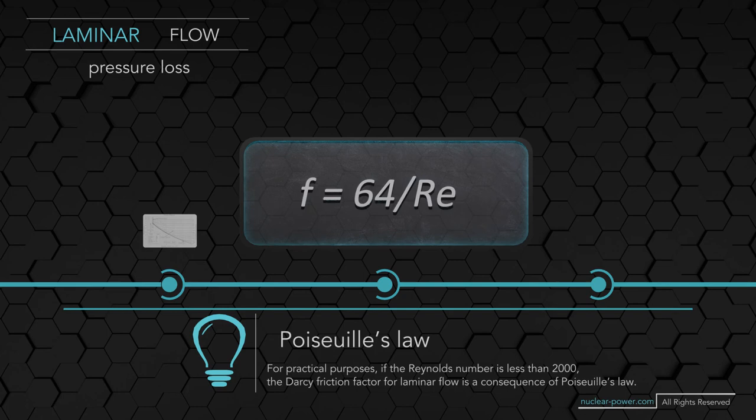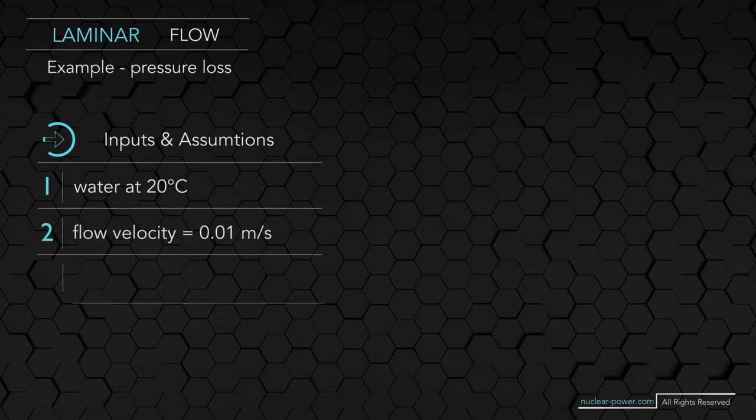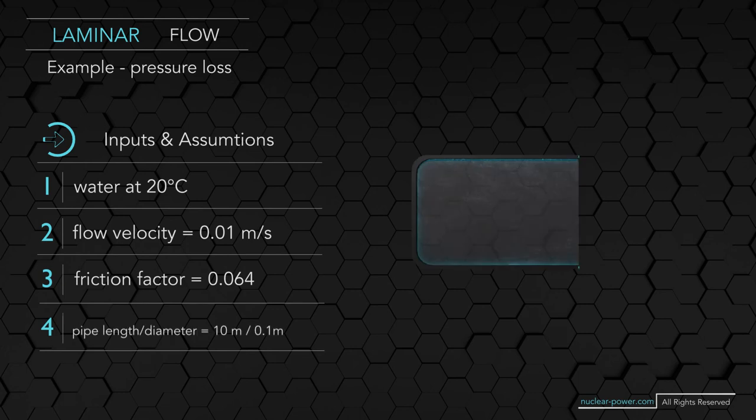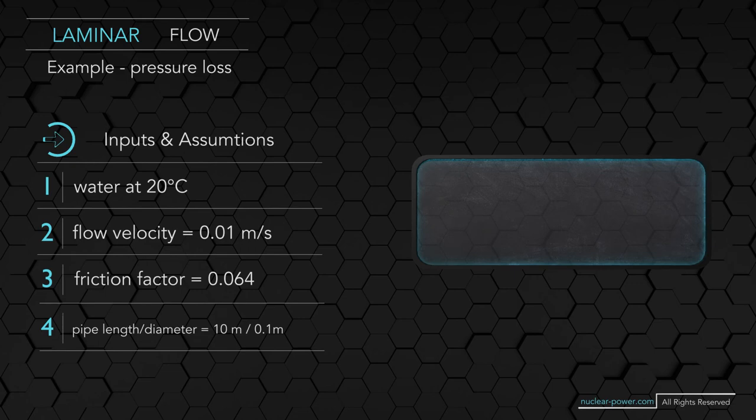For example, let's calculate friction losses that occur in pipe flow due to the effect of the fluid's viscosity near the surface of the pipe. We will assume similar calculation inputs as in the previous example, but we will assume the flow velocity to be 0.01 meters per second. The resulting Reynolds number for water flow in a circular pipe with a diameter of 10 centimeters, where the dynamic viscosity for water at 20 degrees Celsius is 0.001 pascal seconds, is 1000. Using the Moody diagram, we determine the friction factor to be 0.064. Using the Darcy-Weisbach equation, we determine the resulting pressure loss to be 0.32 pascals for a 10-meter-long pipe.